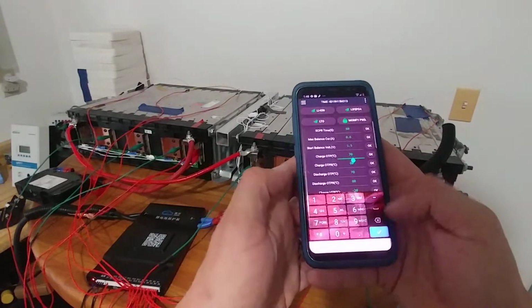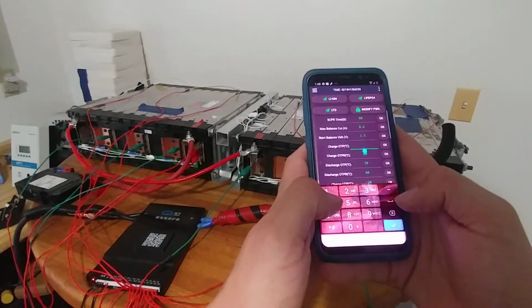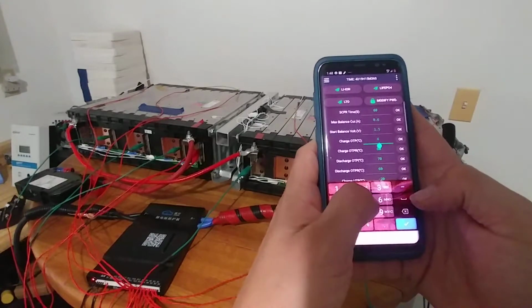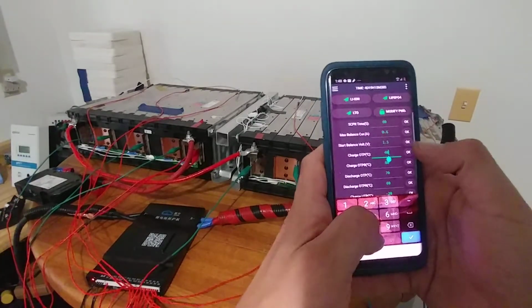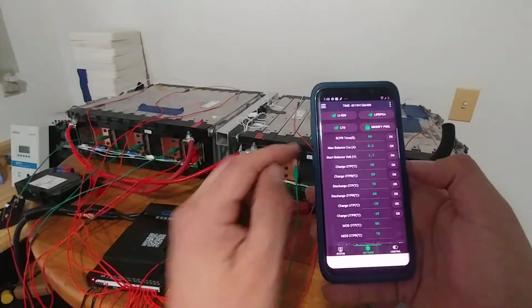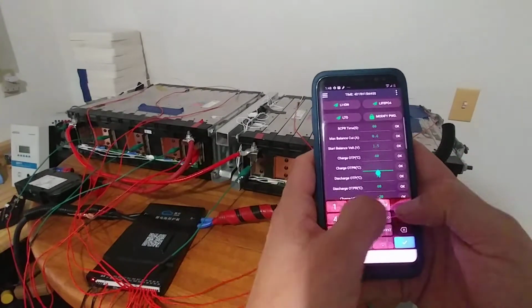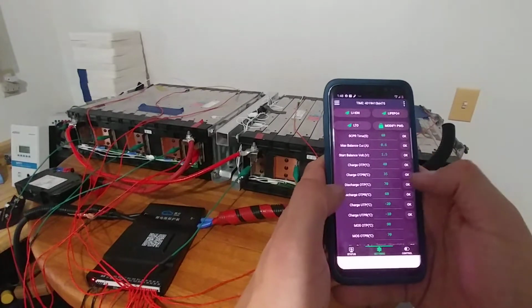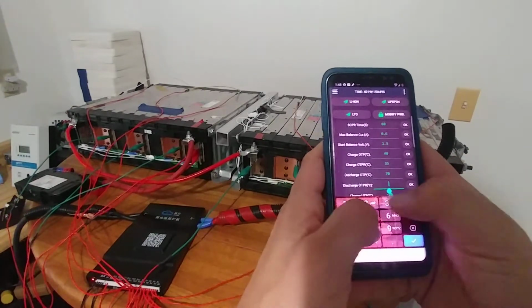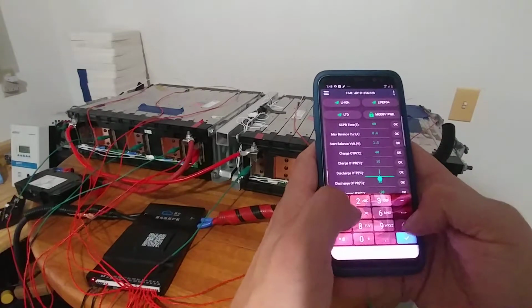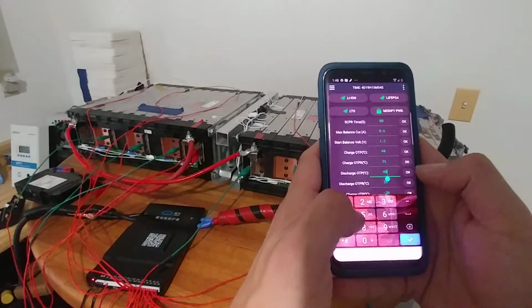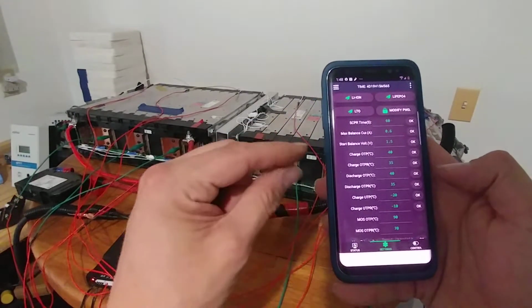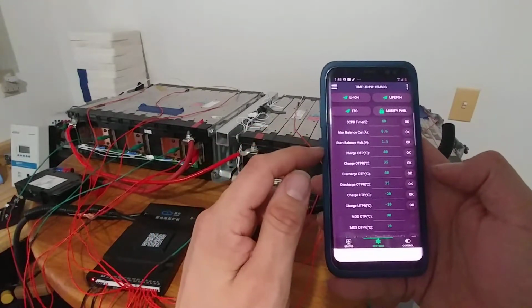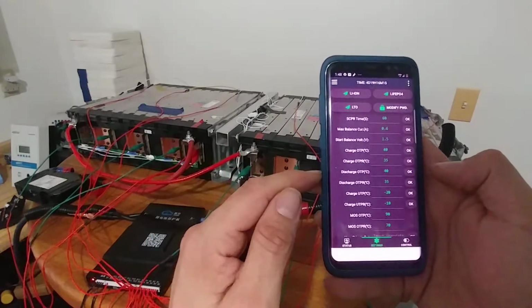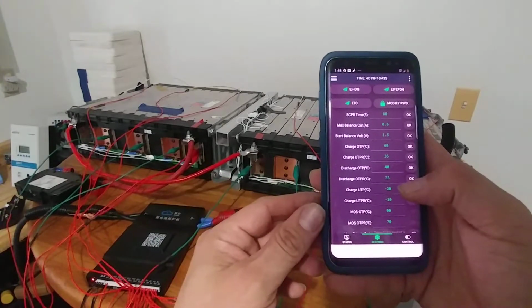So for my particular battery, I'm going to set the protection recovery to be 40, I'm going to say 40 degrees Celsius because it really shouldn't be that high. And you see it errored me out there because my recovery needs to be lower. So if I set this to 35, then this can be 40. And we'll do the same for discharge and charge values, but they are actually different for these batteries. I believe that the charge value can go up to 45, whereas the discharge is still limited to 40, but I'm going to keep them the same for the time being.